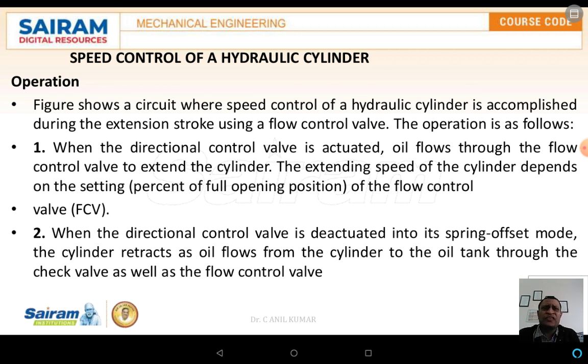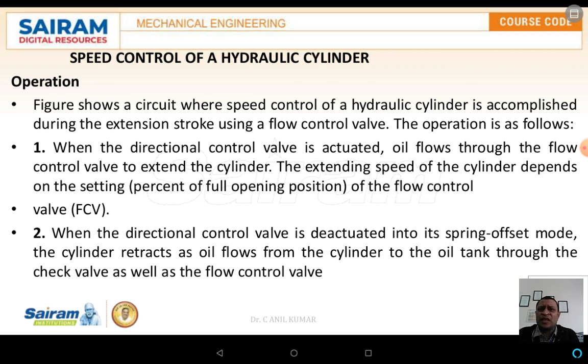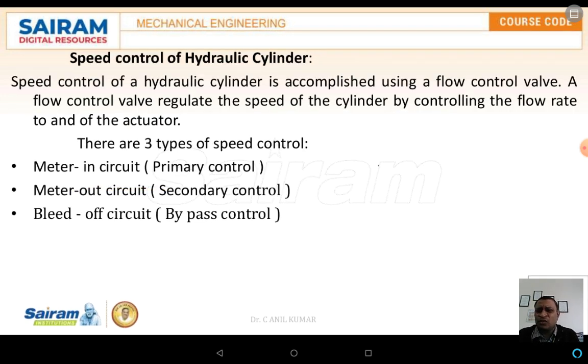When the direction control valve is actuated, oil flows through the flow control valve to extend the cylinder. The extending speed depends on the setting of the flow control valve. When the direction control valve is de-actuated into spring offset mode, the cylinder retracts as oil flows from the cylinder to the tank through the check valve and the flow control valve. Speed control of hydraulic cylinders is accomplished using a flow control valve.